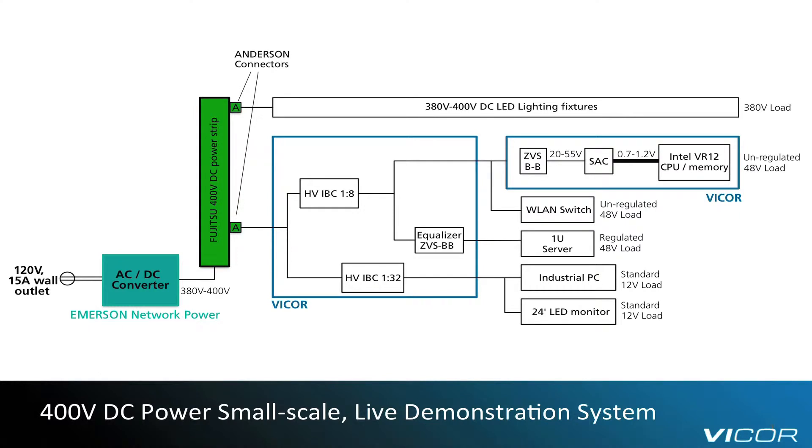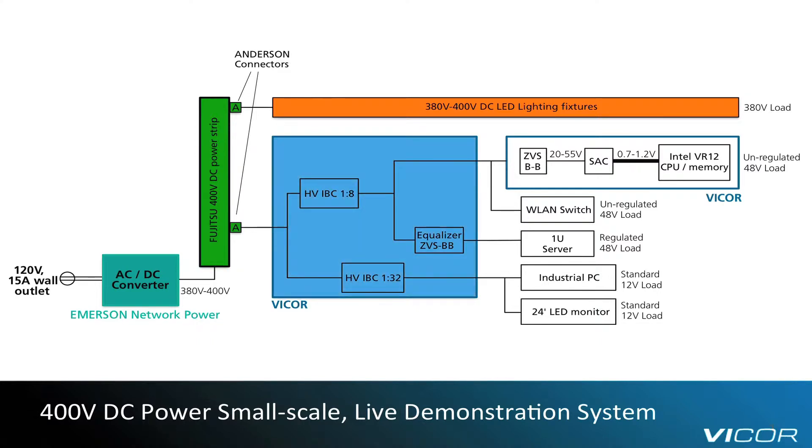Second, a 400V DC rated power strip with 600V DC rated connectors. Third, an LED lighting fixture powered directly from the 400V DC strip. Fourth, an interface board with Vicor products specifically designed to address 400V DC powered telecom and datacom equipment. Finally, several data center type loads: a Vicor reference design for Intel VR12 servers, a LAN switch, a 1U server, an industrial PC, and an LED backlit monitor.